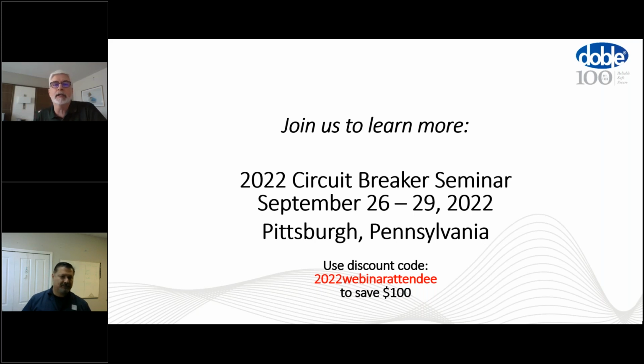So the first one is from Nick. Is there an industry guideline, either IEEE or IEC, or industry recommendation, on the acceptable operating limits for sulfur dioxide and moisture for SF6 breakers? And if there's no industry standard guidance, is it advised for equipment owners to use guidance from the SF6 breaker manufacturer? Well, if I understand, the question is about sulfur dioxide? I think it's acceptable operating limits on levels of SO2 and moisture in the gas.